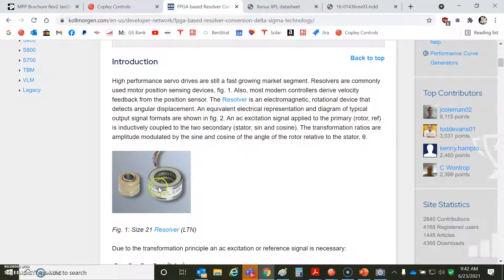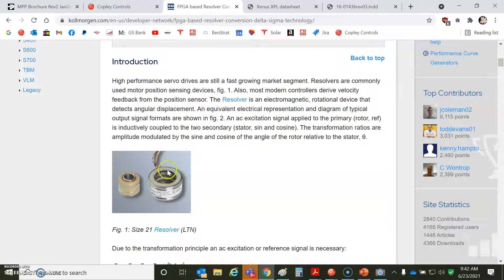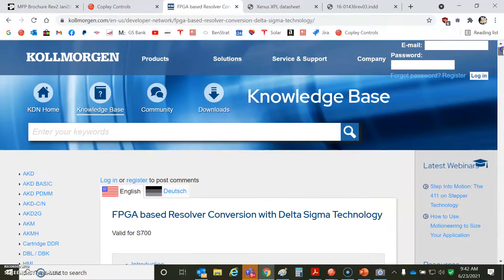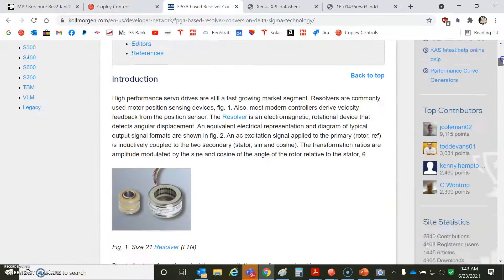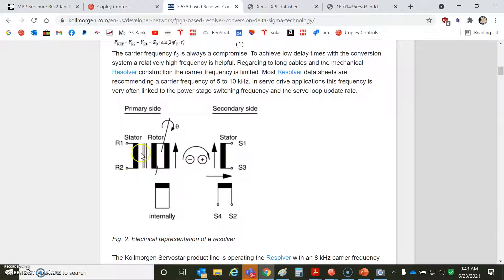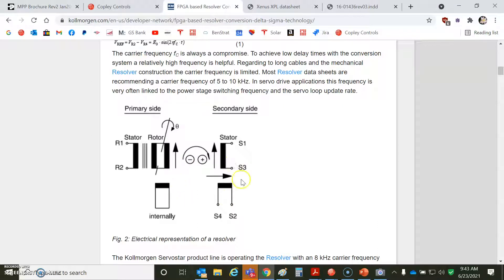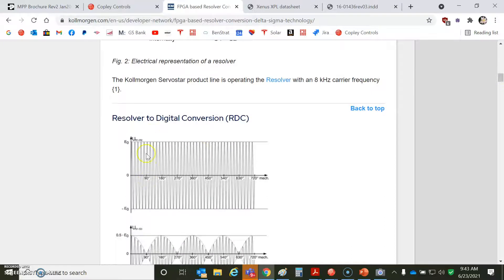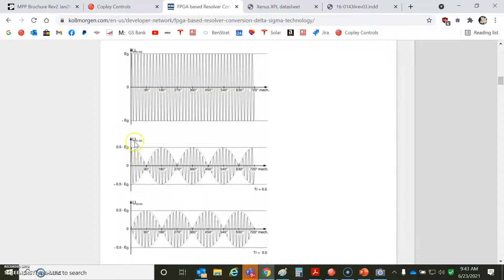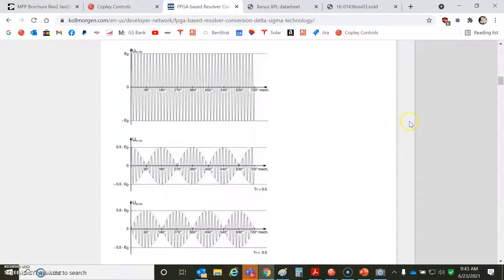But the basic idea of a Resolver is that it's a winding. And then so this gets mounted on the stator with the cables, and then you rotate the rotor. So the stator and the rotor and the signals are excited and picked up by this part, and they're induced through the rotor. This is a little bit of theory of operation from the Kollmorgen guys. I'm glad it's not in German. But, again, you can see as the stator stays still and the rotor rotates, you get a different pickup for either mutual inductance, full signal gets through for a sine wave, or none. If it's 90 degrees, nothing gets through. And so here's the excitation of a high-frequency sine wave, like 8 kilohertz or 10 kilohertz. And then the coils pick it up as a modulated sine or cosine and sine wave, which gets demodulated in the drive, and you get a nice sine and a cosine, which makes a nice circle.